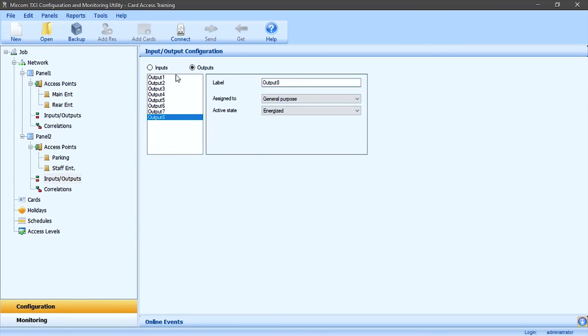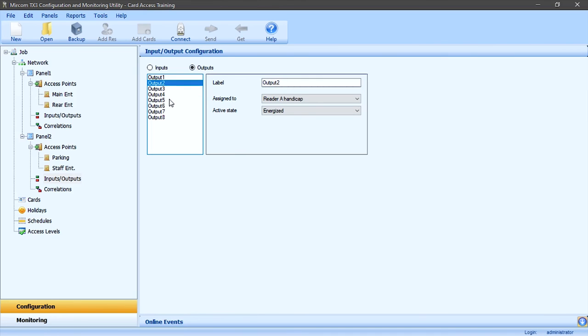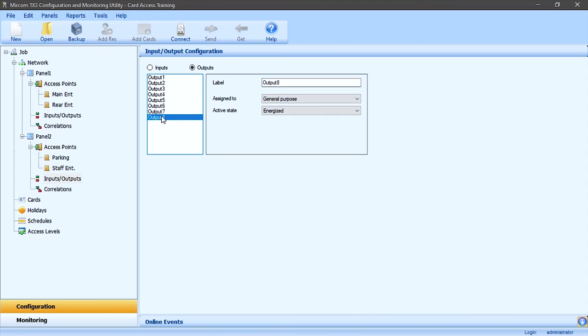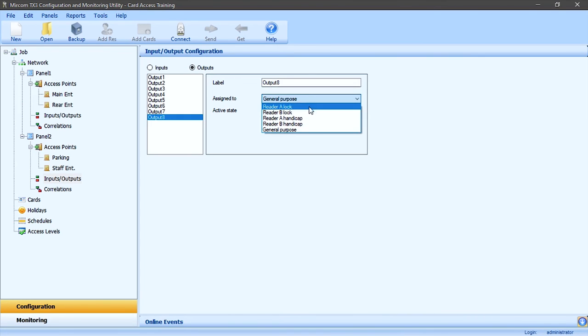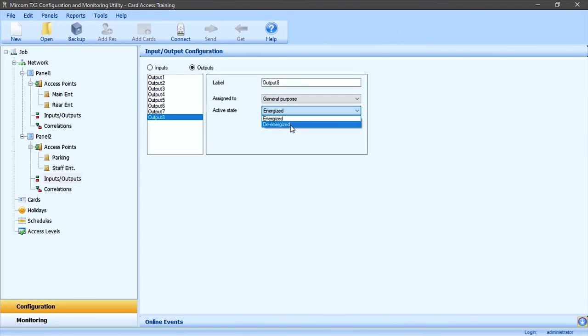Outputs 1 and 5 are assigned to each reader's lock and operate the door strike. Outputs 2 and 6 are assigned to operate accessible doors. This works in conjunction with cards that have the designated accessibility privilege via the handicap checkbox. Please note that outputs 1 to 6 are dry relay contacts and outputs 7 and 8 are wet relay contacts which output 12 volts DC and provide a maximum output of 700 milliamps on a single output or a combined output of 1 amp total.